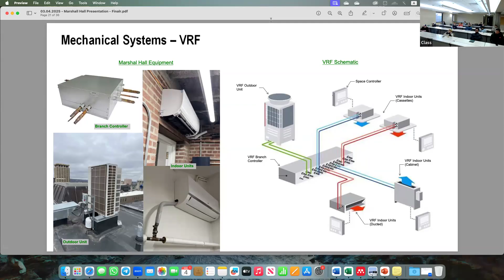And then in the rooms, you have your indoor unit, and that defines the heating and cooling of that specific space. So again, each of these indoor units can be in either heating or cooling, and they can share that load amongst them. But the big difference is that they're using refrigerant that's distributed throughout instead of water. And those were really just used in specialty spaces or corner offices where the load was going to be a little bit different than some of the other rooms, just to make sure that we were allowing those rooms to fluctuate differently from the building.